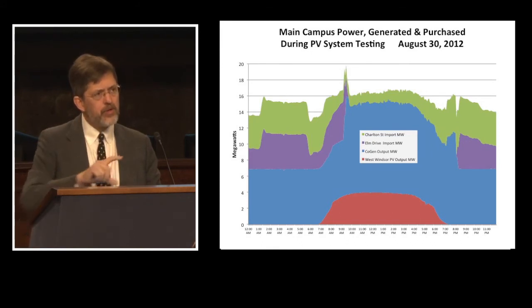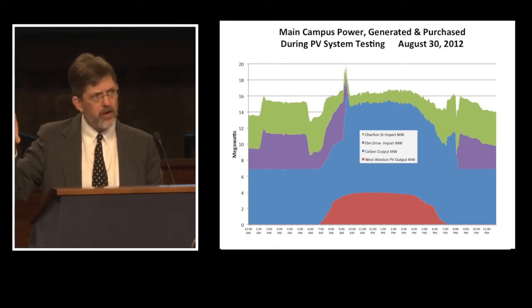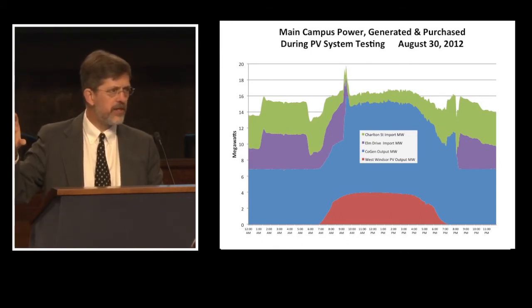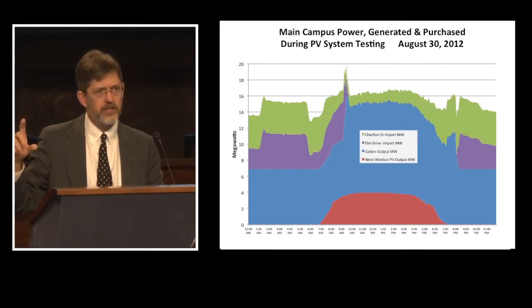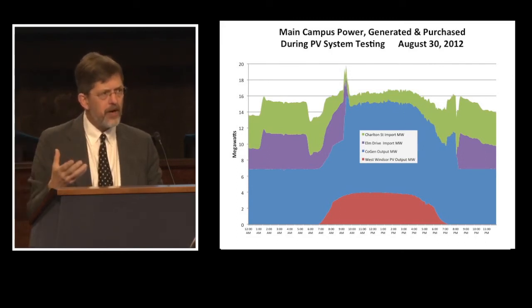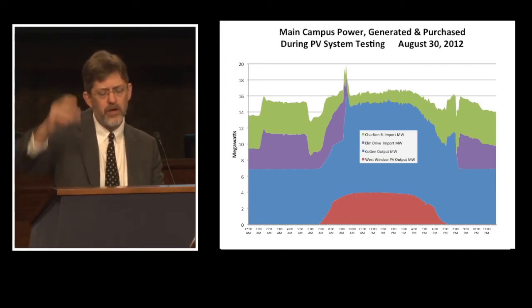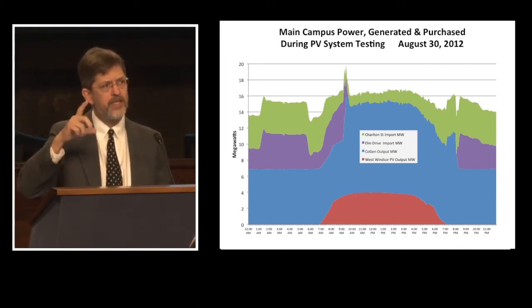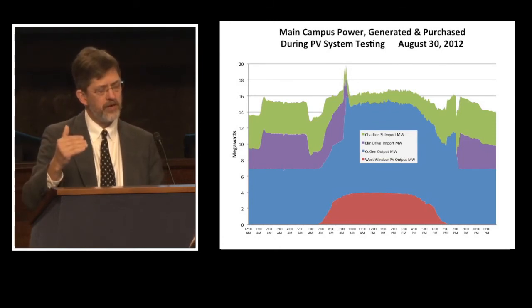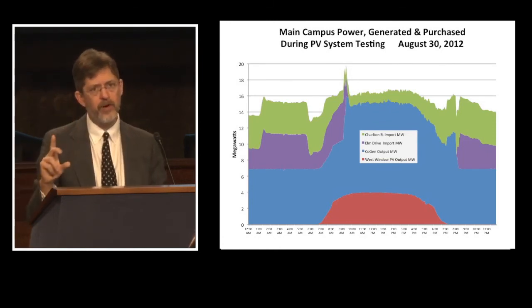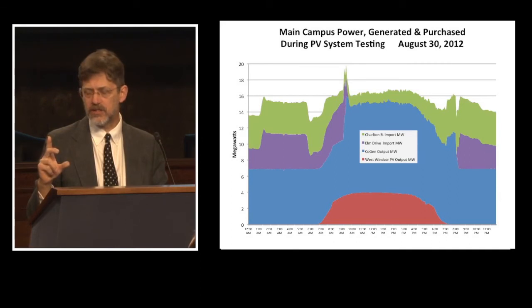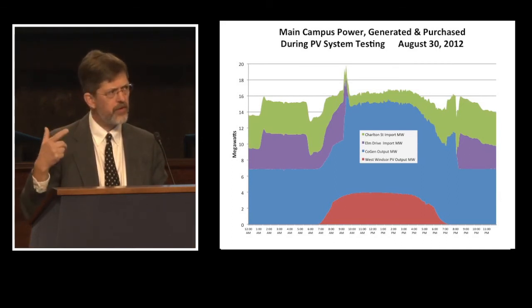The blue is the power production on our CHP, the cogeneration microgrid or substation. About half load, 7 megawatts, in the middle of the night, and we ramp the throttle forward to full load when power prices exceed our marginal cost of generation, then back down when the power price is lower than our marginal cost.